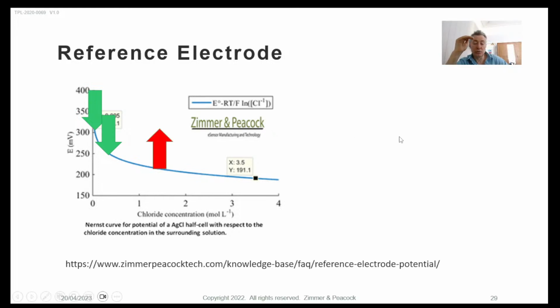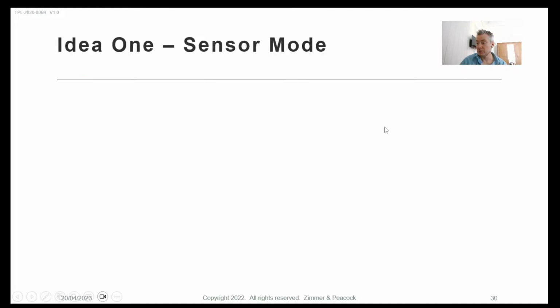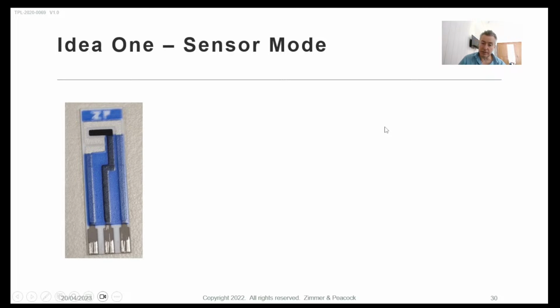Now what's happening is you're measuring pH versus the reference, but of course if the reference is changing, then your pH, let's say that my reference did this, the pH value would do this. If my reference did this, the pH value would do this. So some of your oddness is not coming from your working electrode, it's probably coming from your reference electrode. How do we fix it? Okay, this is something that we do at ZP. It's not perfect, but I will describe it.